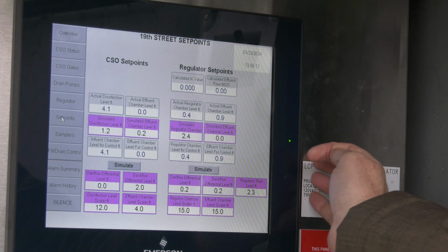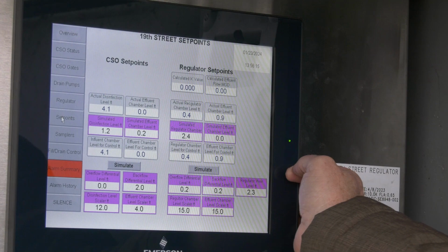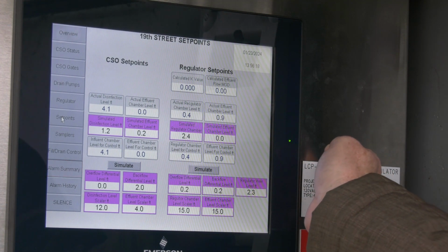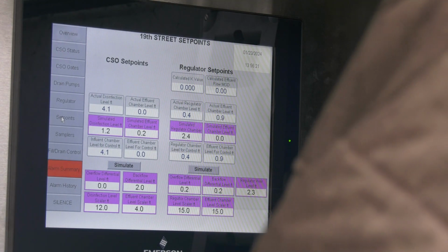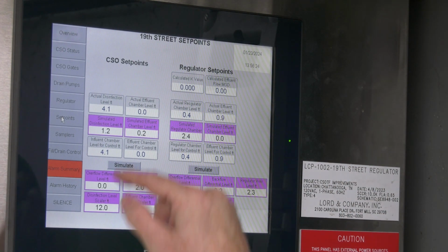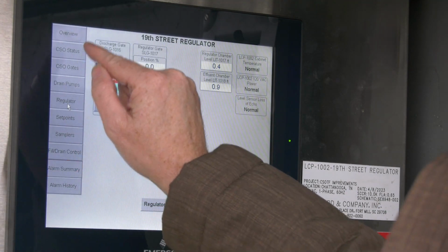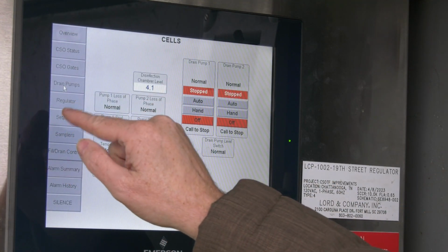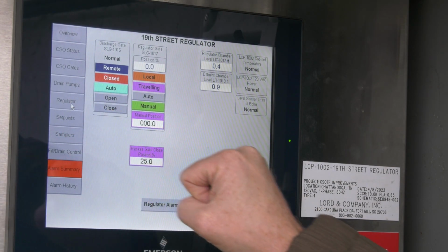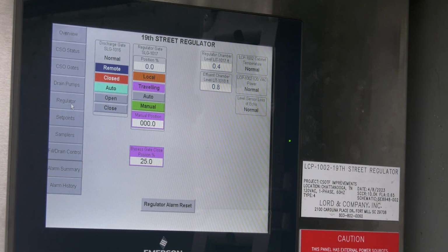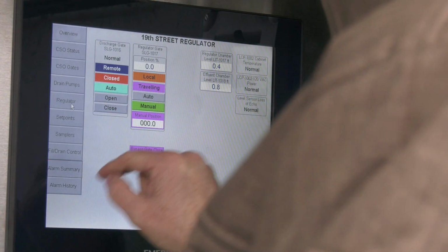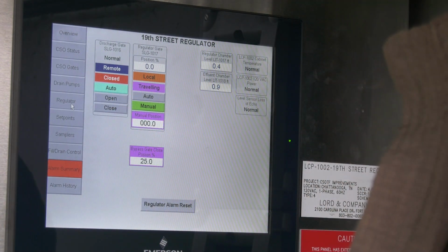All right, so when the regulator level gets above 2.4, that triggers the CSOs to fill. Okay. And there's a valve. Which valve is it? Regulator. All right, so it's the discharge gate, SLG 1016. When we're in an overflow condition at the CSO, we open discharge gate SLG 1016 to discharge to the river. Okay. All right. And that's pretty much all the controls of the regulator.